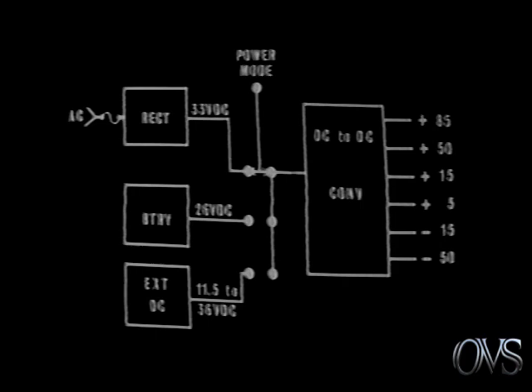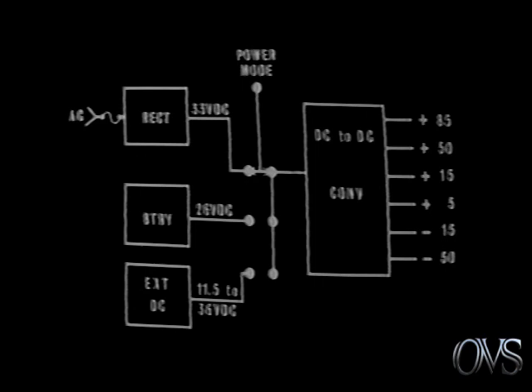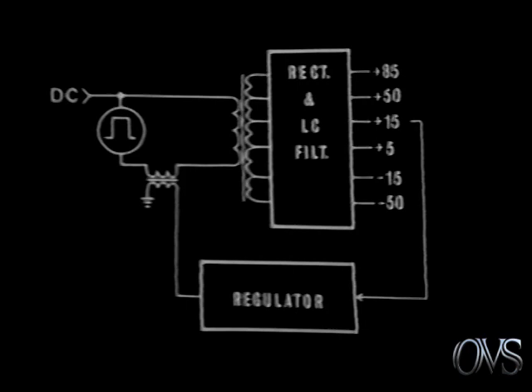A unique, highly efficient DC to DC converter is used to provide the DC voltages required in the operating circuits of the 1700. This converter changes the selected DC input to AC. This AC is then converted back to the DC levels required by the 1700 circuits. Let's look in more detail at how this conversion is accomplished.